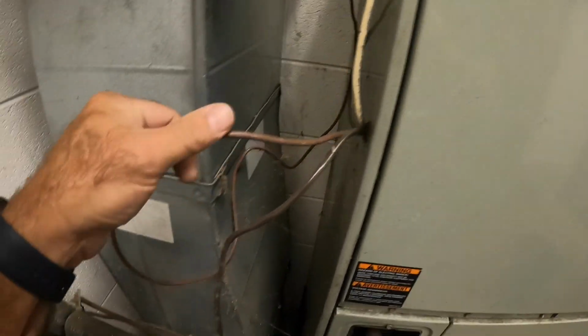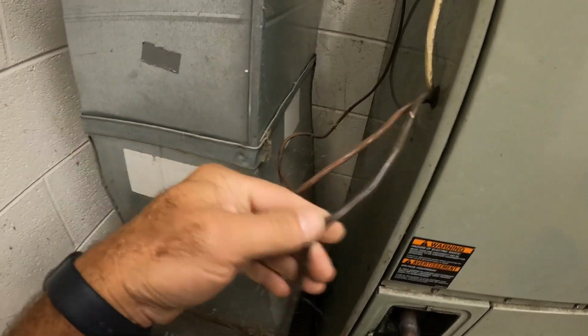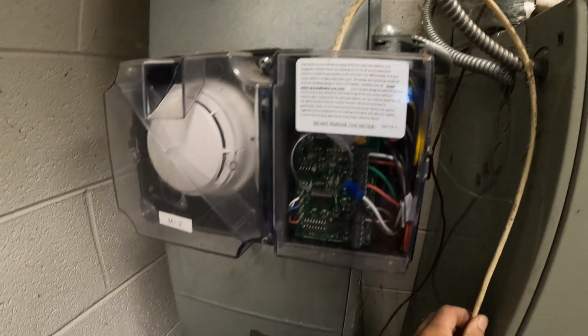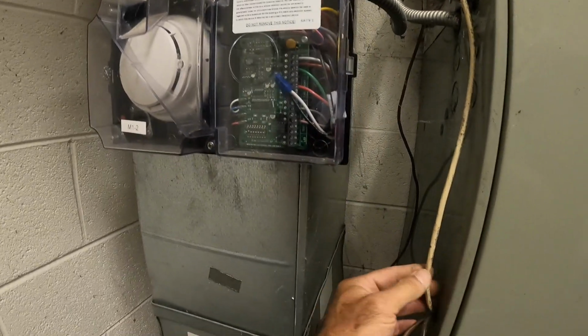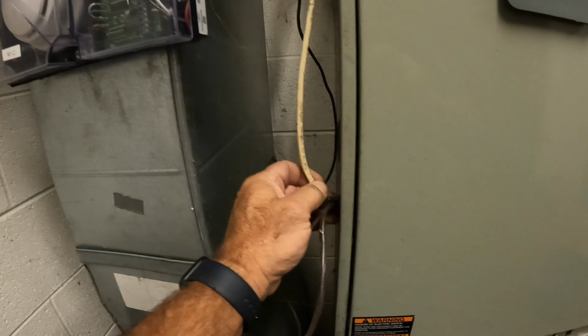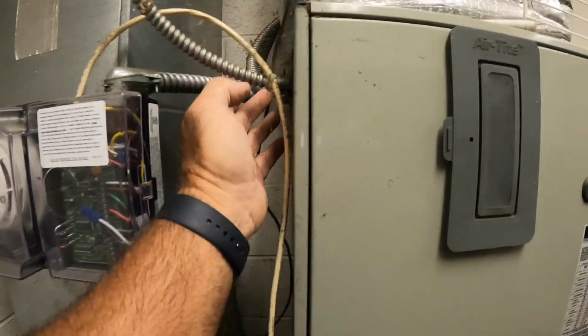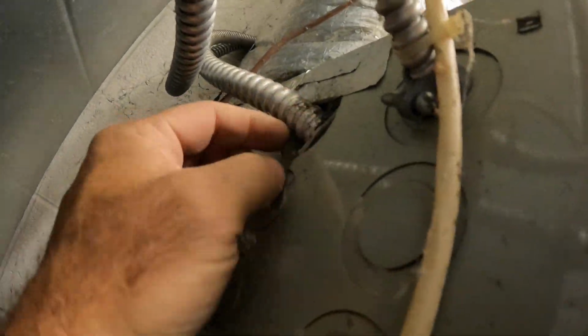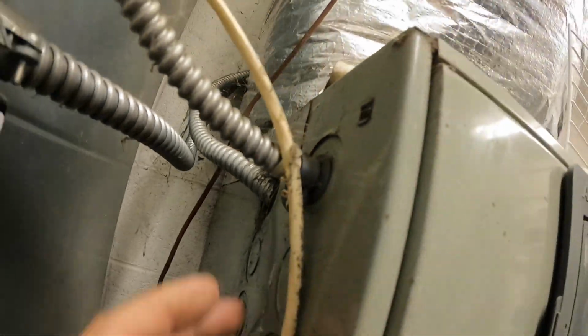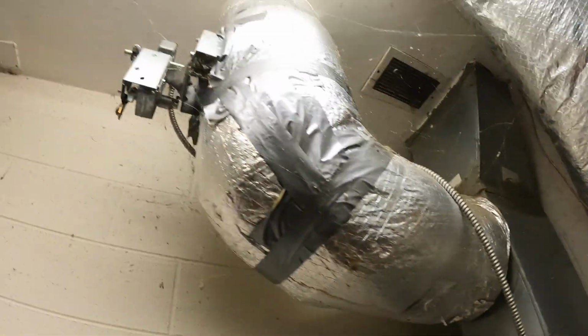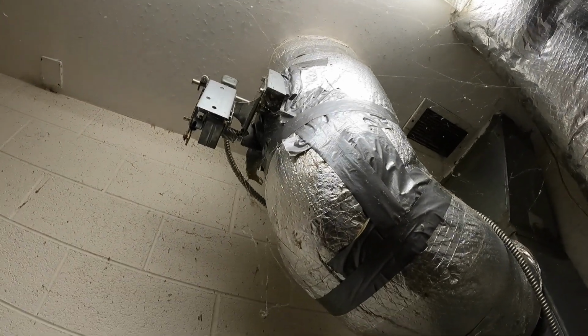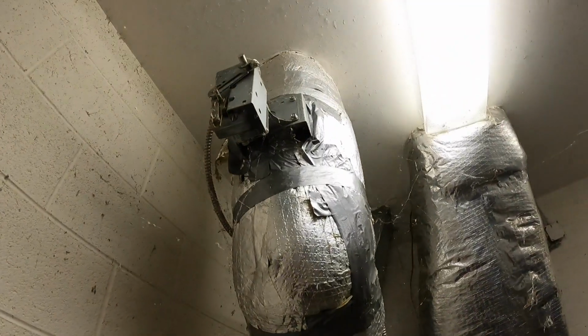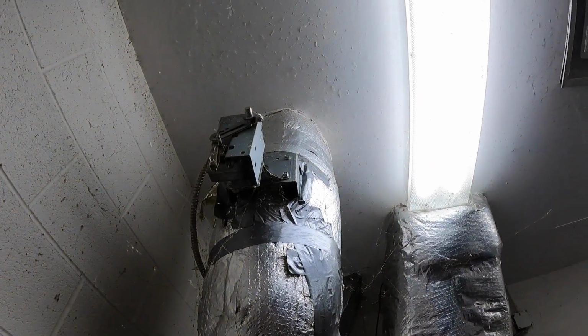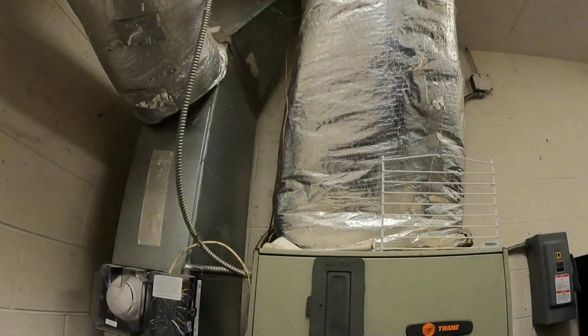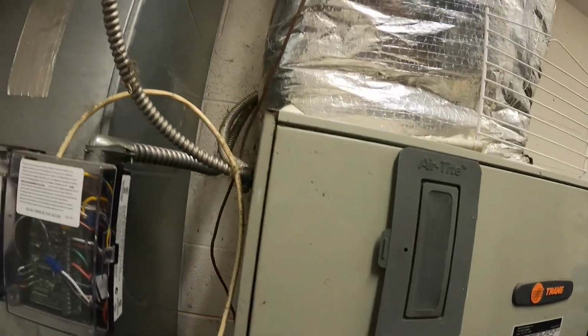Thermostat wire. This will be coming in from the building control system. This is going to the outdoor unit. And this is for the smoke detector that shuts the unit off if it senses smoke in the duct there. So we'll have to get that unhooked. Power comes in right up here. Oh, look at that nice knockout. And then this guy will be fresh air damper. Have to see if that's 12 or 24 volts or 120 volts, so we can figure out how we're going to have to rig it up. But we'll take this door off and we'll be able to tell more about it.